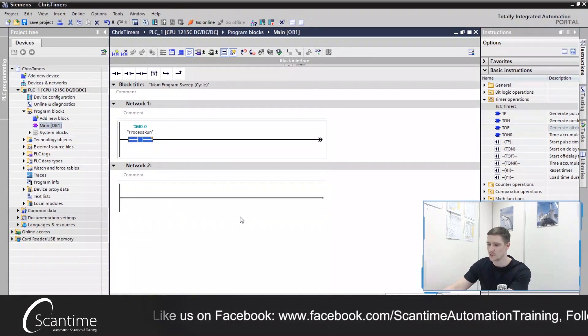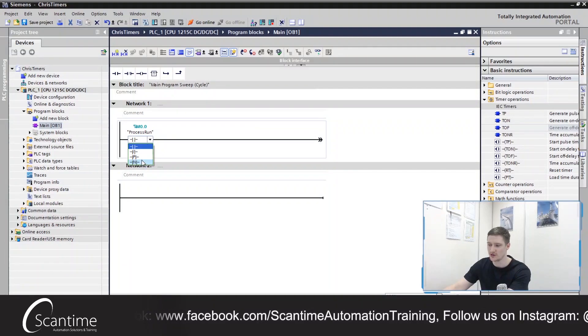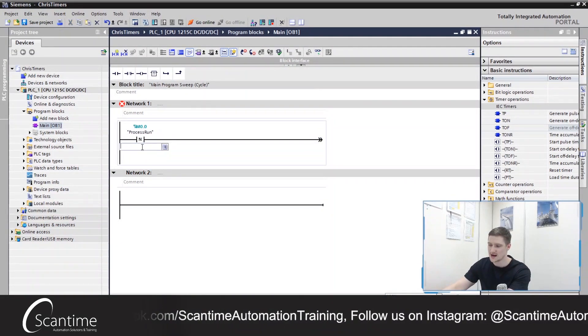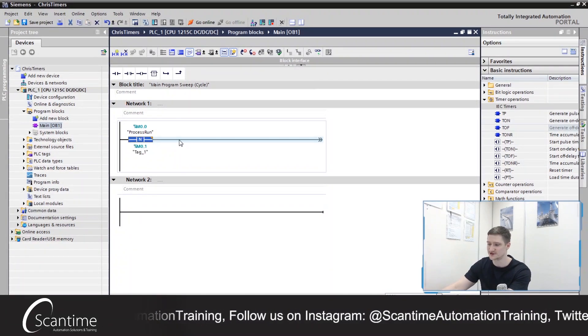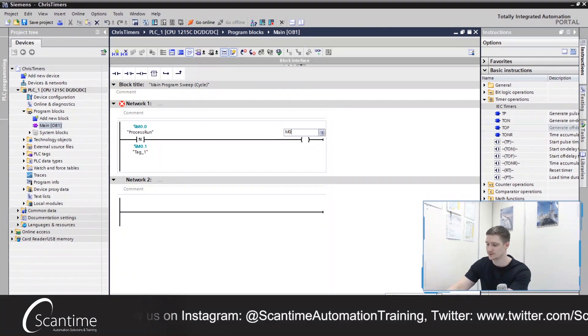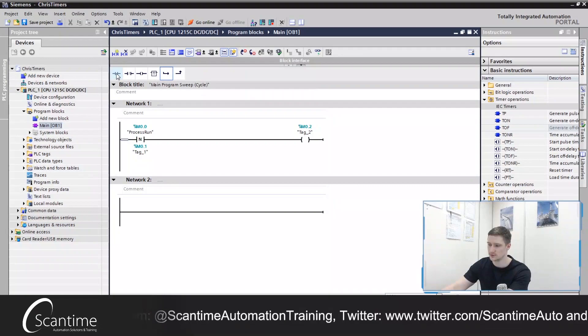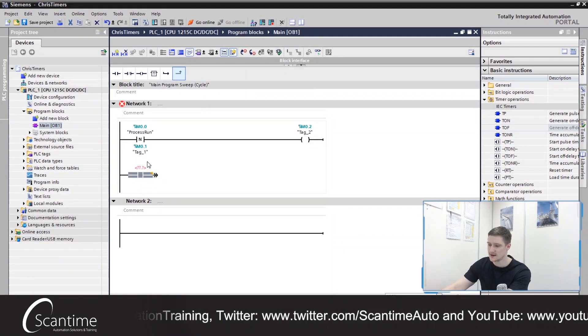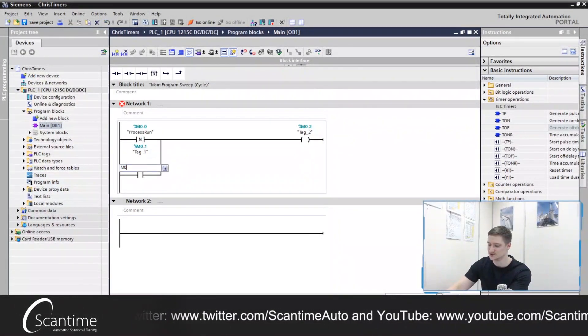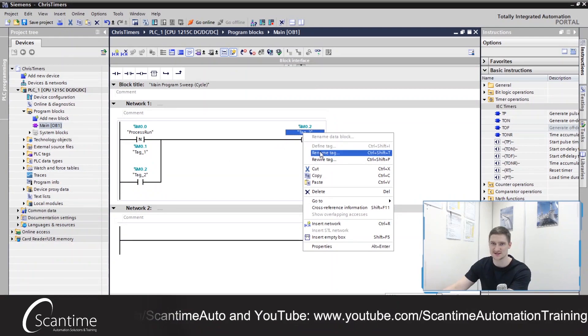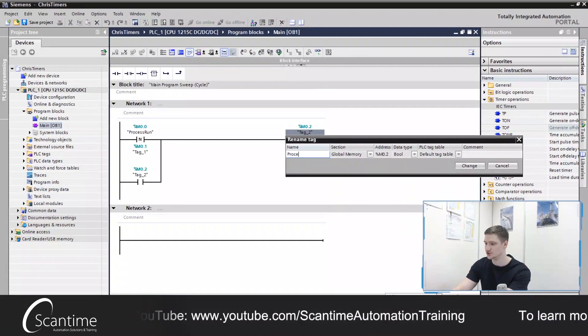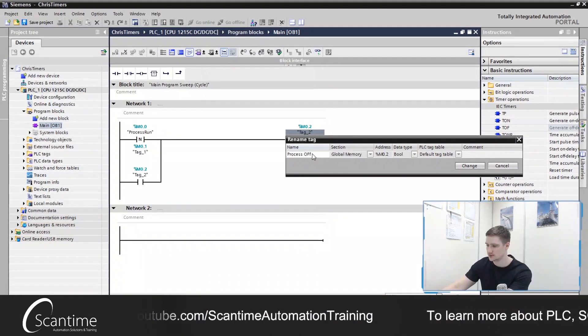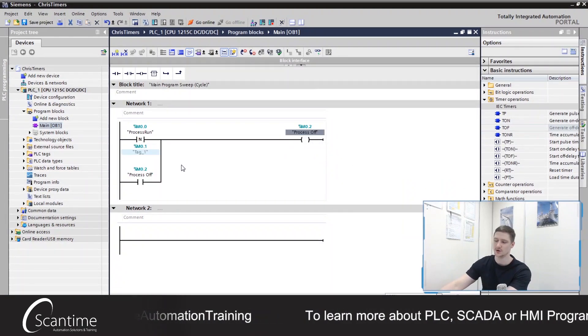Then what we're going to do is we're going to have this trigger on the negative falling edge. I need to assign a storage bit to it, I'll just assign M0.1 for example. And what we're going to do here is we're going to latch on a bit, M0.2. And this is going to be our signal to tell us the process is turned off, which is going to be that enable signal for our timer effectively. So let's rename this to process off for example.